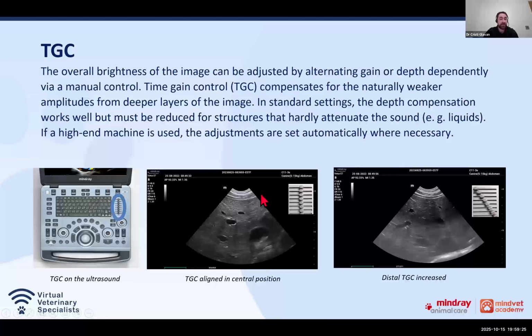What this means is that we'll increase or decrease the level of gain, so the level of brightness, at certain levels, and everything will go in a line. We can see it in a central position, and we can see the difference when we are decreasing the gain proximal and increasing the gain distal. Always try to have a play with this, but be aware that I have seen some examples where the gain was increased at the near field, really proximal, and when we scan small structures, consider adrenal glands, if we have a nodule and a really bright area here, we might miss small mineralization, small changes in the adrenal glands. So always try to adjust.